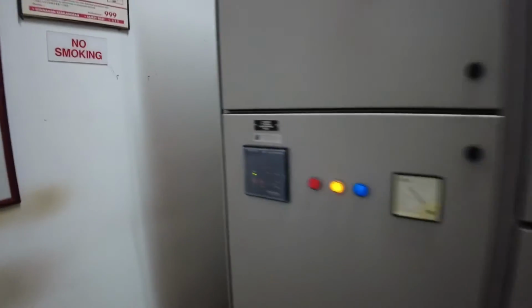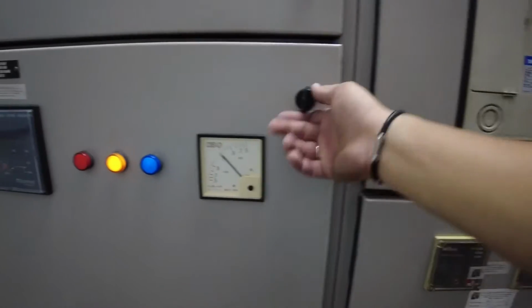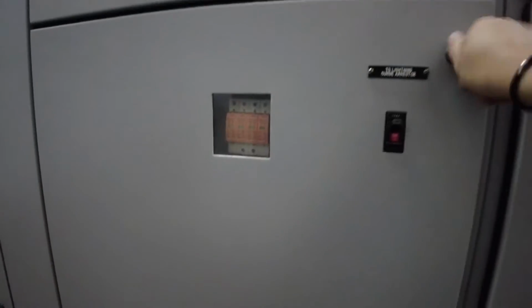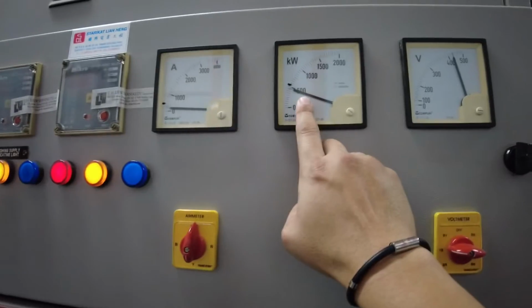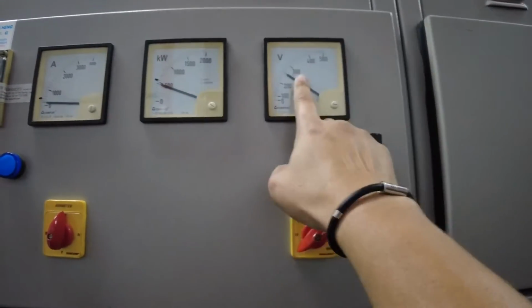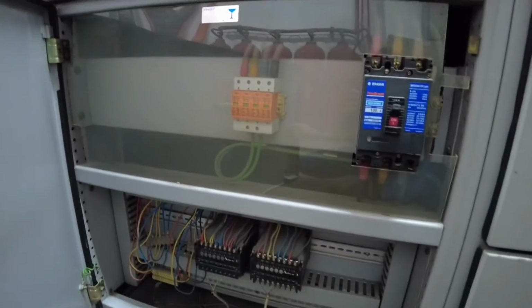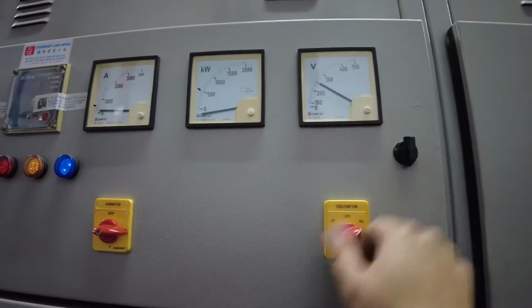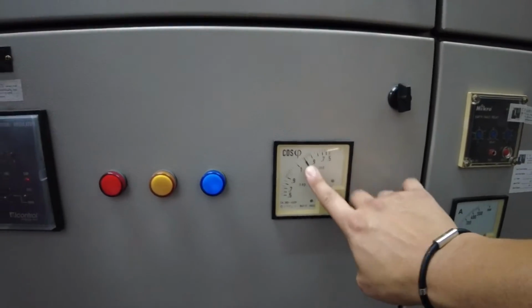Let's check power factor value. See this, is there any tripping? So far okay, but need to further check the capacitor bank. This is the surge arrestor. Surge arrestor okay. About 500 kW. Voltage is okay. Calibration not expired. This is MSB number 2. Surge arrestor okay. Voltage is okay. Calibration okay, ACB okay. Power factor above 0.9.